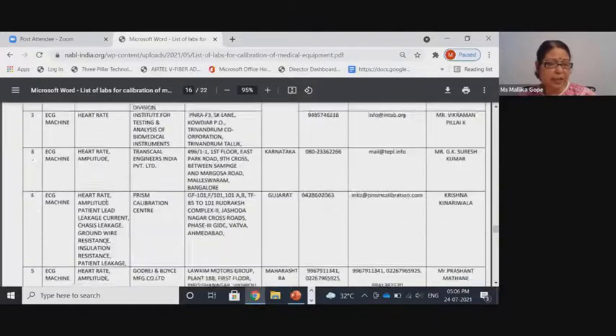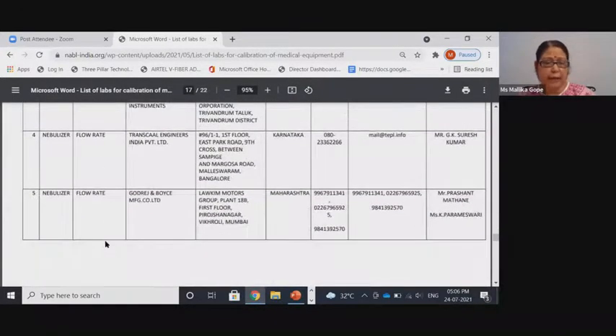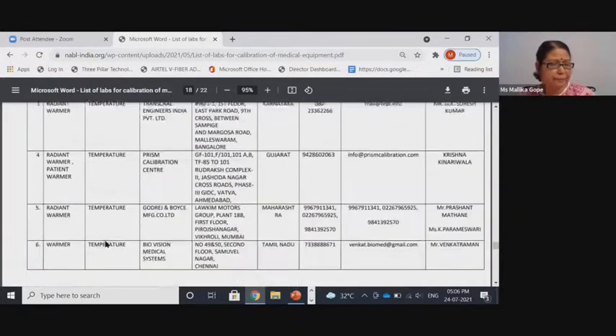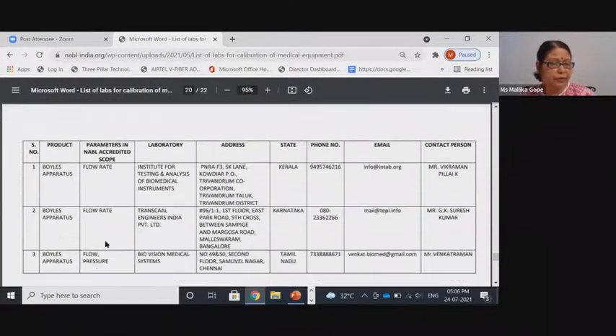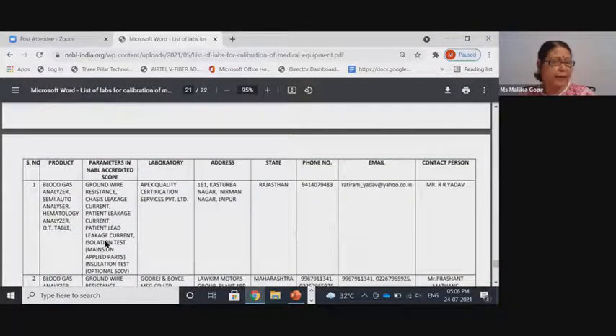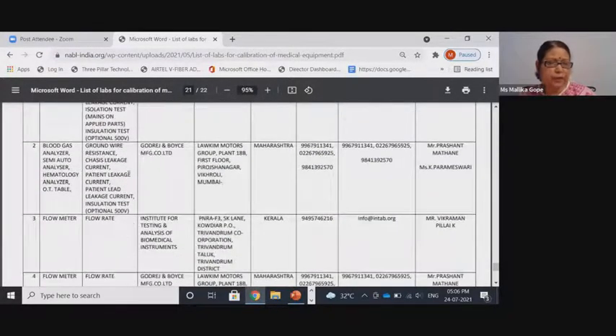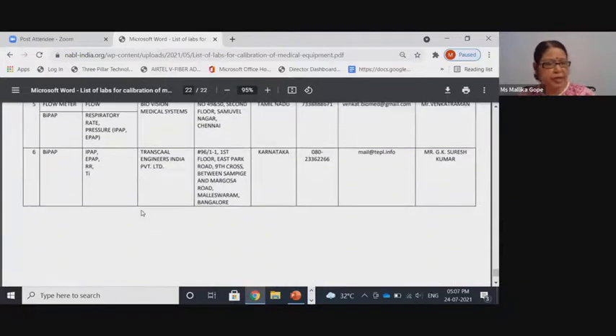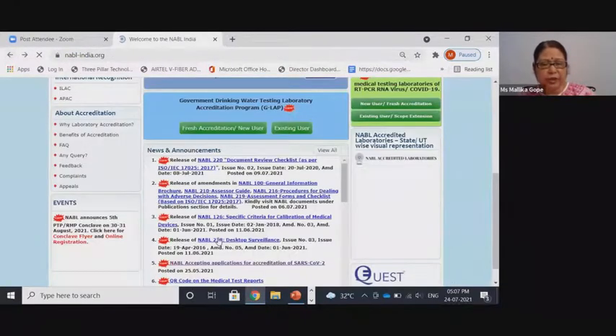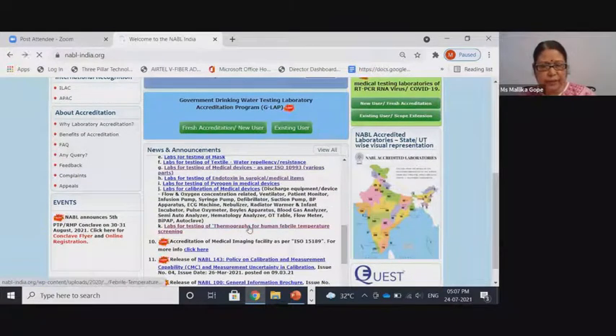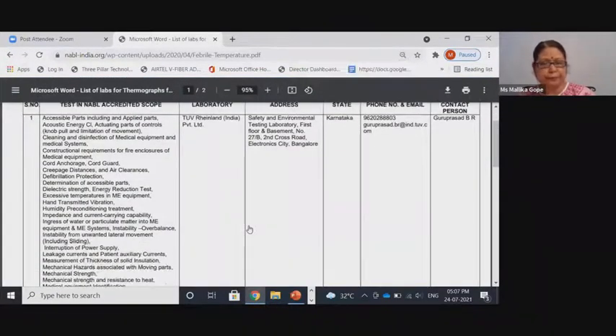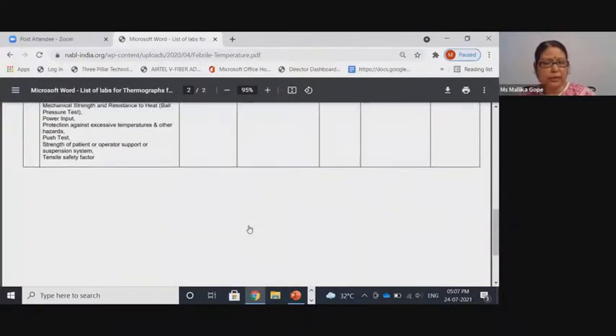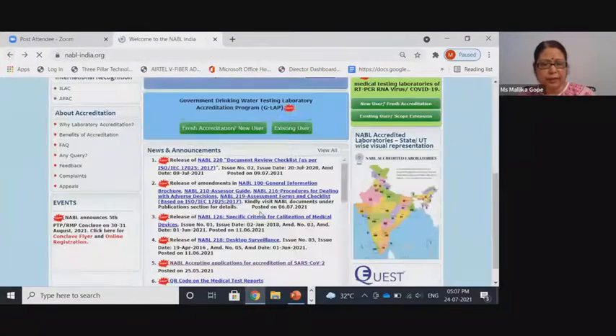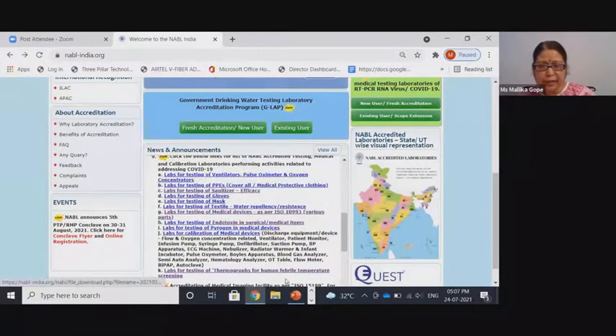refer to the list. ECG machines, nebulizer, these also can be calibrated, radiant warmer, autoclave, Boyle's apparatus, blood gas analyzer, semi-auto analyzer, hematology analyzer, OT table. In these, the various parameters which are required to be calibrated are mentioned in this list. We have also given one list for thermographs, calibration for testing of thermographs. So these are the labs which are available for testing of medical devices and equipment in the NABL website.